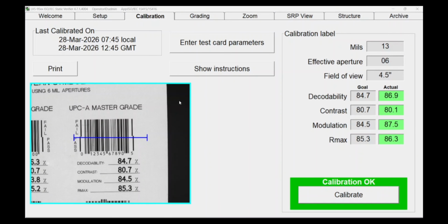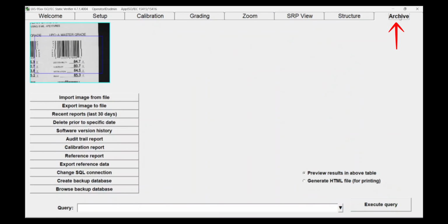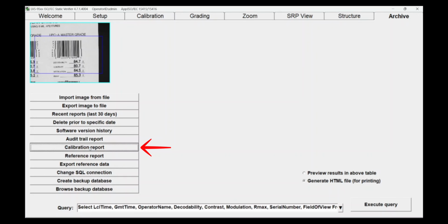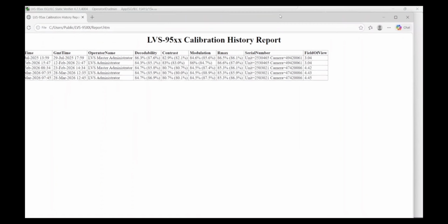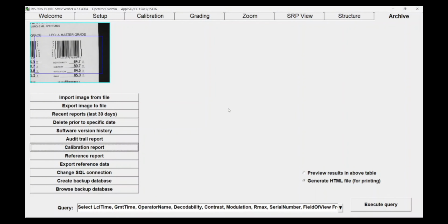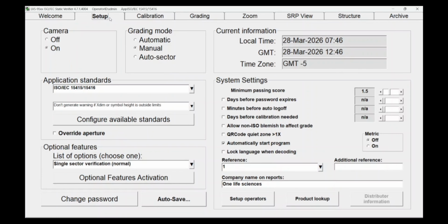To confirm your calibration, you can go to the Archive tab and select Calibration Report. This will generate a page showing the history of calibrations for this unit, along with the user who completed the calibrations.